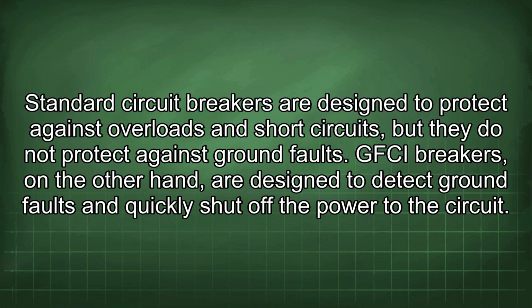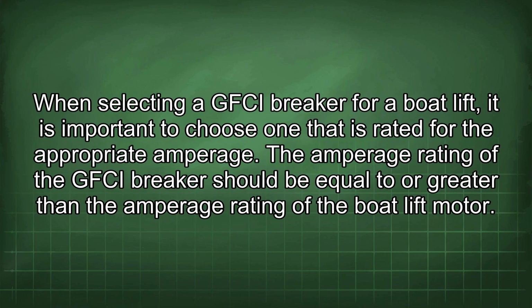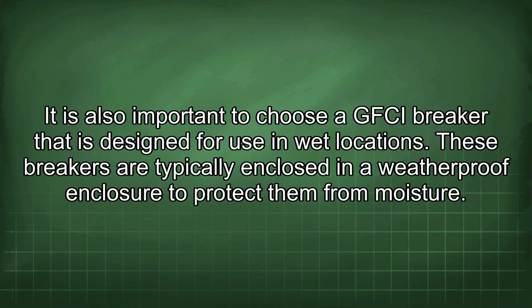GFCI breakers, on the other hand, are designed to detect ground faults and quickly shut off the power to the circuit. When selecting a GFCI breaker for a boat lift, it is important to choose one that is rated for the appropriate amperage. The amperage rating of the GFCI breaker should be equal to or greater than the amperage rating of the boat lift motor. It is also important to choose a GFCI breaker that is designed for use in wet locations. These breakers are typically enclosed in a weatherproof enclosure to protect them from moisture.